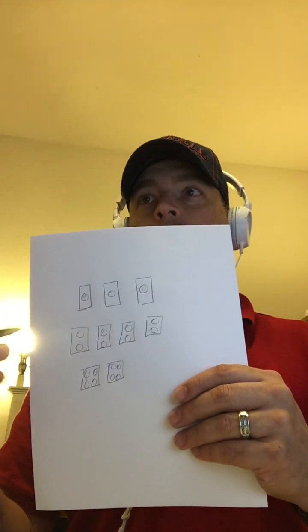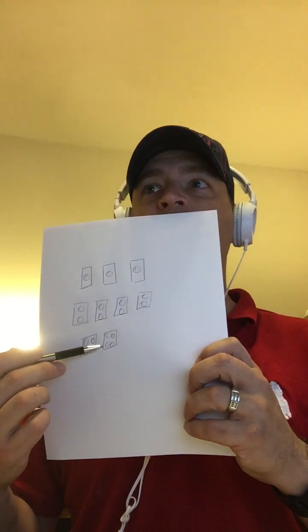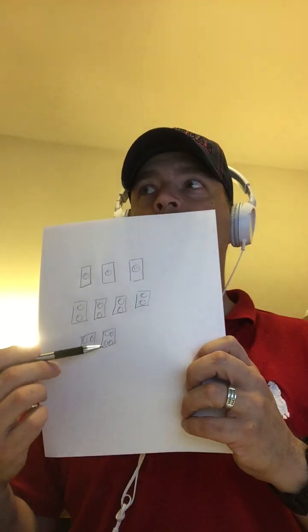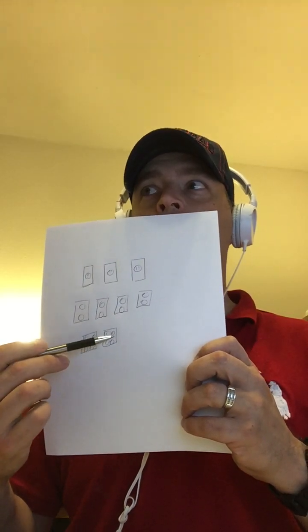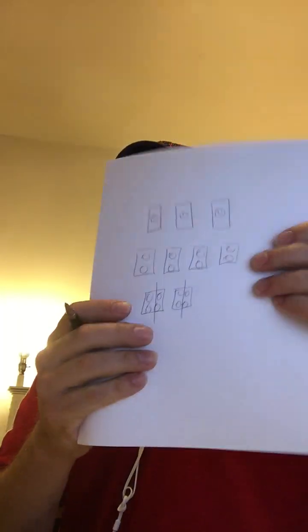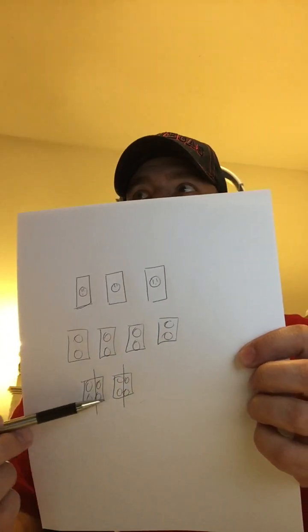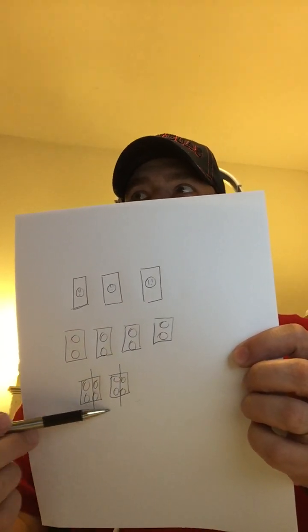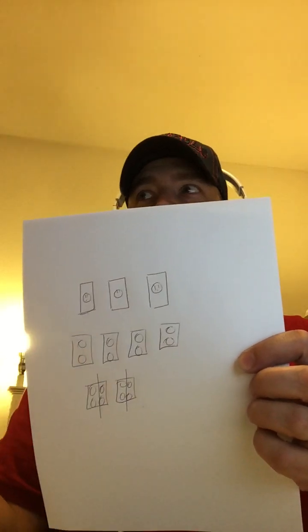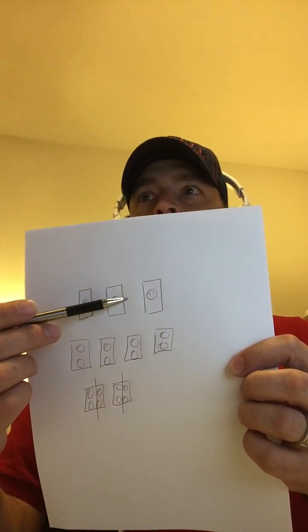Even the quads? The quads would be 180 VA each gang there, so you're looking at 360 VA for each one of those quads, because you're doing 90 VA per receptacle. But the regular calculation is still basically the gang of the box that you're doing that 180 VA against. So down here you'd be doing 180 times 2 anyway, whether you're doing them all together on one piece of equipment or if they were on a wall. Either way, the only thing that changes are these little ones up here at the top.